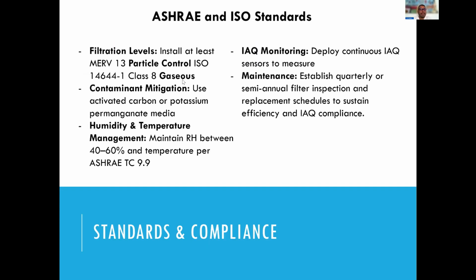For the ASHRAE and the ISO standards, it was paying attention to the filtration levels. Like Katie said earlier, ASHRAE sets the standards, and NAFA will help exercise those standards in practice. ASHRAE recommends a MERV 13. What NAFA is saying is if it's a single stage, we're using MERV 13. However, if it's double stage, you could use a MERV 8 pre-filter with a MERV 13 final filter. Contaminant mitigation using activated carbon. Temperature and humidity management has to be between 40 and 60%, and that's in regards to technical committee 9.9.